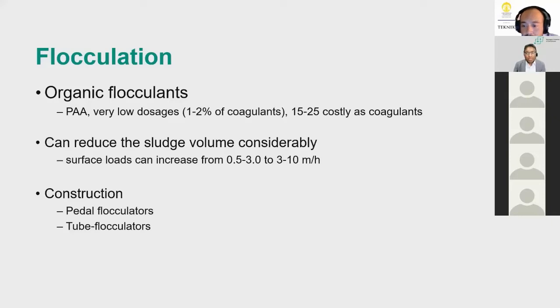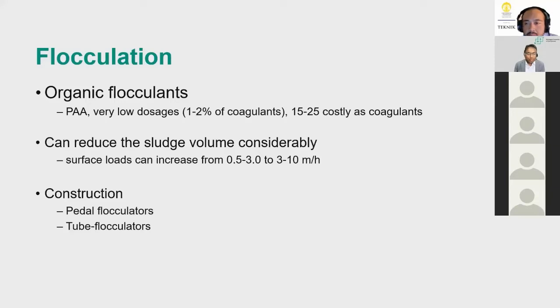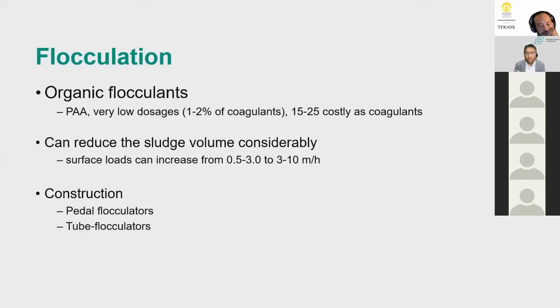Flocculation is the second stage after initial rapid mixing. Organic flocculants — polyacrylamides — are typically used at very low dosages, about one to two percent of coagulant amounts. Although they cost 15 to 25 times more than normal coagulants, because so little is used, the cost difference does not matter in practice.